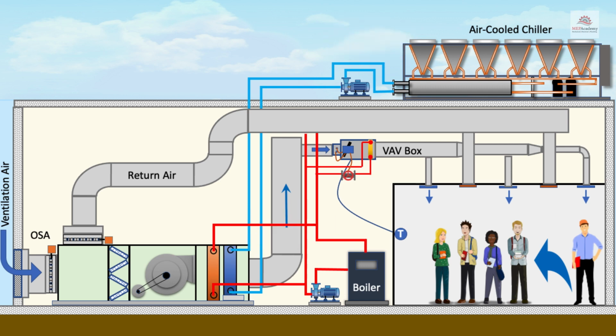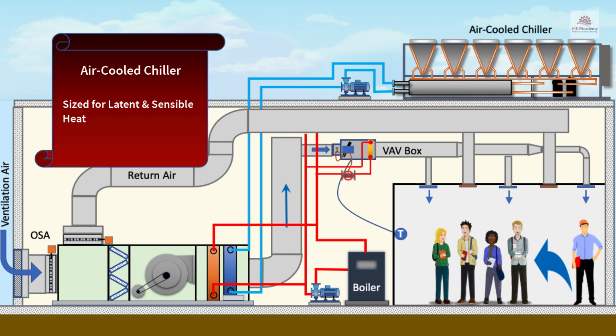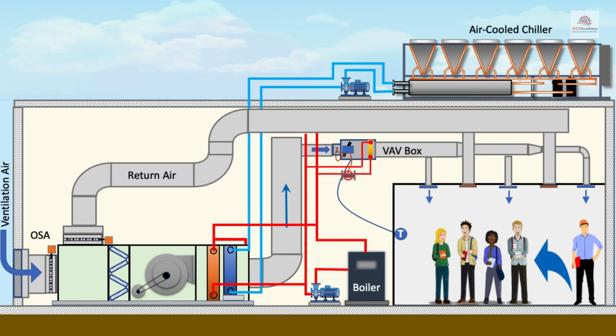The important thing to note is that the air handler and chiller are sized to treat all the latent heat coming in for ventilation and internal latent loads, in addition to the sensible load. The chilled water coil in the air handler is sized to provide latent and sensible cooling.